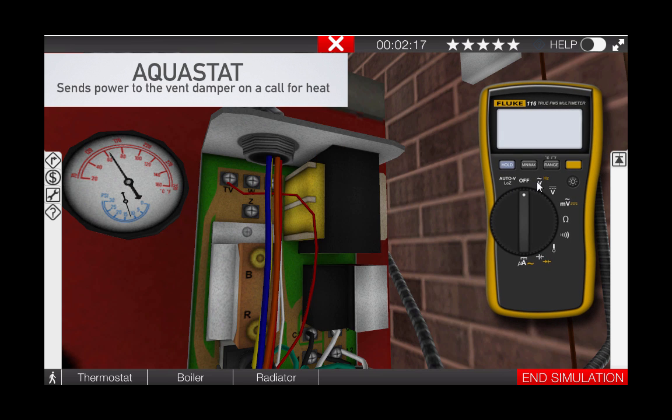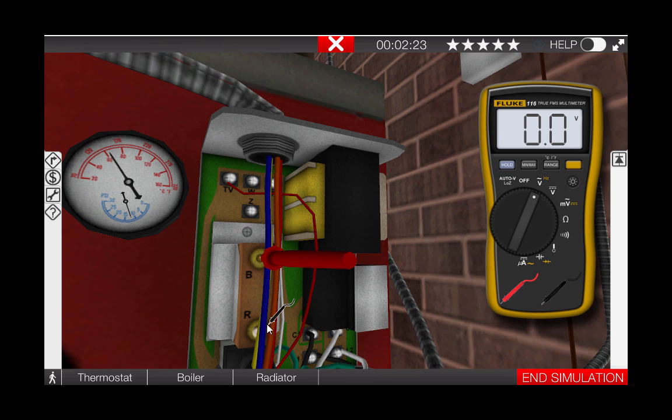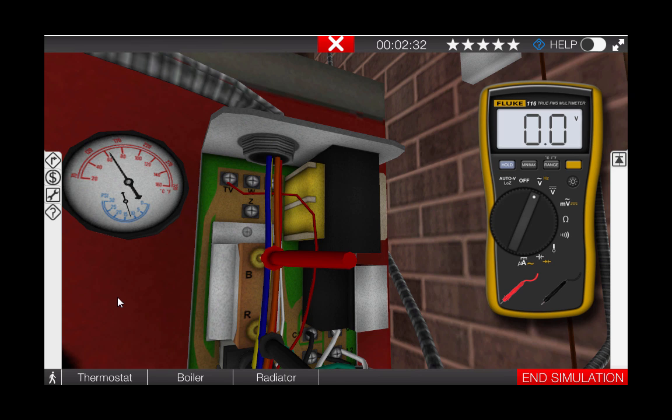Taking the digital multimeter out of the toolbox, we're going to click it to AC volts and place each of the leads across the B and R terminal on the high limit. As we can see here, we have a reading of zero volts indicating that the high limit switch is closed and therefore the vent damper should be operational.